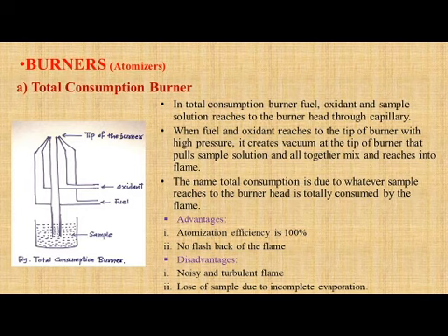It also depends on the ratio of fuel and oxidant and what type of element we are going to detect or measure. That also matters in the selection of fuel and oxidant. This burner has some advantages. The first one is that atomization efficiency is 100%, and there is no flashback of the flame.